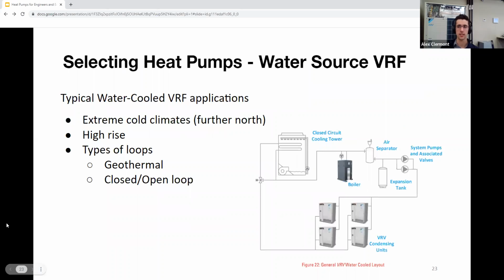Next, we are changing gears and talking about water source VRF. We talked about air source quite a bit, but where are water source VRF systems applied? A typical application is extreme cold climates, for example further north, up in northern Maine or up in Canada. These are commonly seen. Water source systems are also used for high-rise applications, hotels or office buildings. These machines need to absorb and reject heat from a water loop, and that's often a closed loop, as seen here on the right with the boiler and cooling tower. But we are starting to see more and more applications where these are used in geothermal applications.